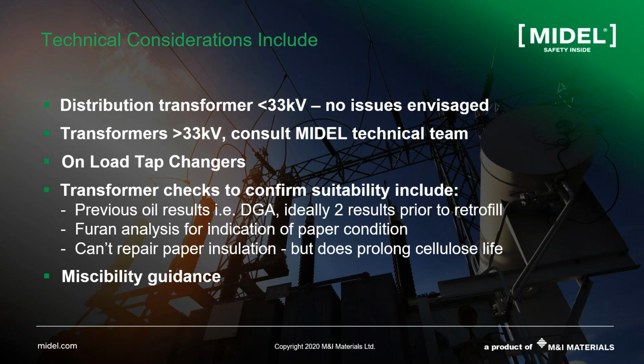Another very important aspect is the on-load tap changer. We know that the on-load tap changer is a critical unit to regulate the voltage of the grid, especially with increased solar and power generation. Because it involves mechanical movement and esters have higher viscosity, we need to assess if the on-load tap changer is suitable for a retrofill, or if we can keep it with mineral oil if it is in a separate tank.